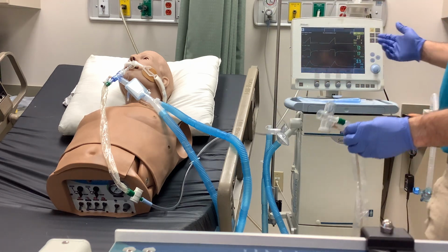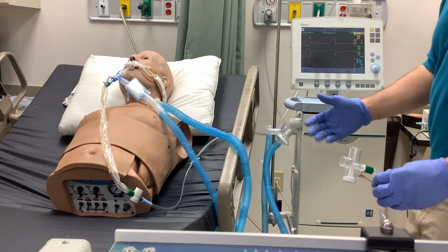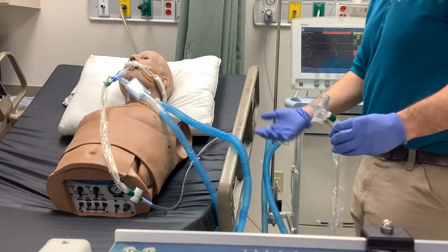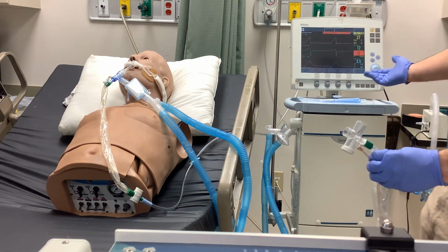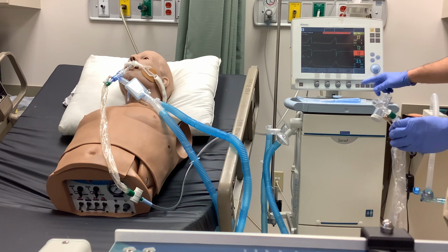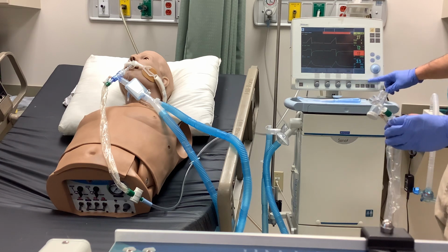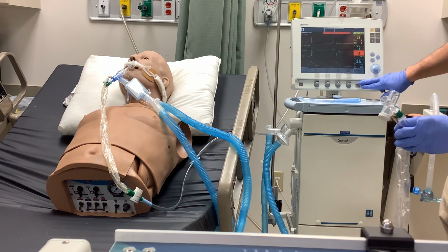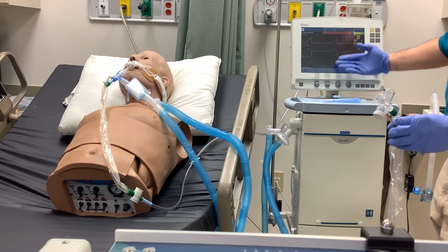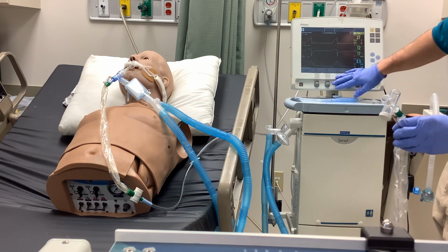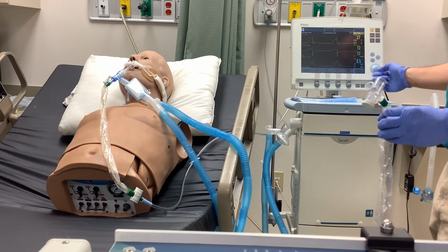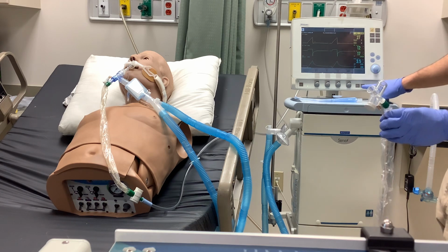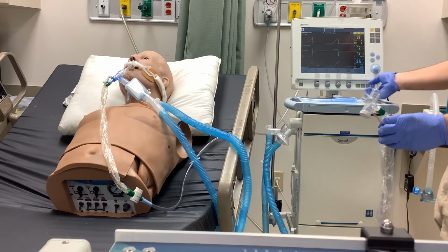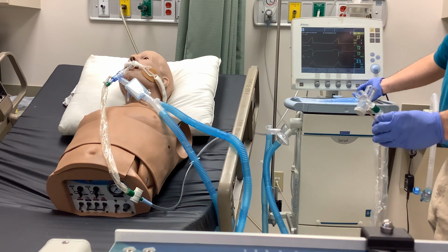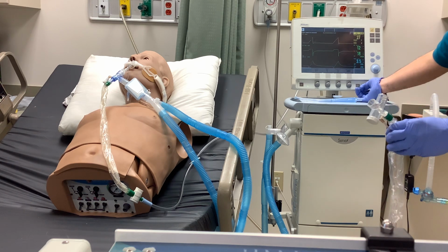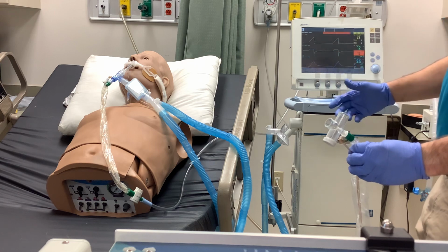On most ventilators today, there's going to be some type of suction button, increase O2 button, O2 breath, or what have you. On the Servo i ventilator, it's been broken off, but there's a clear plastic pane that can be raised up and dropped back down over, but it's been broken off of this one. But you'd lift that up, and underneath here, there's an O2 breaths button right here.